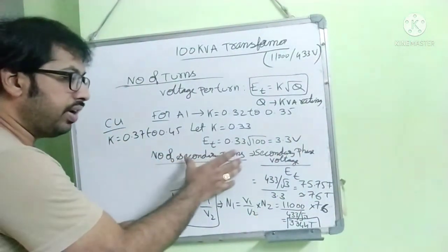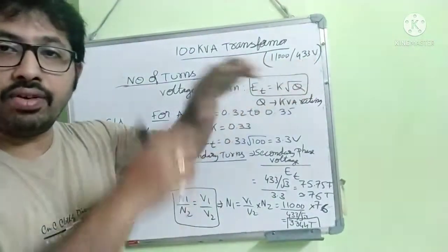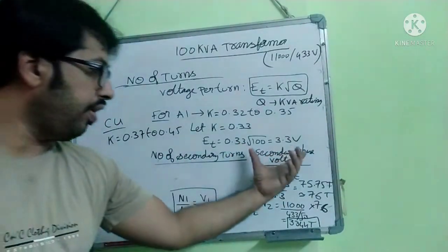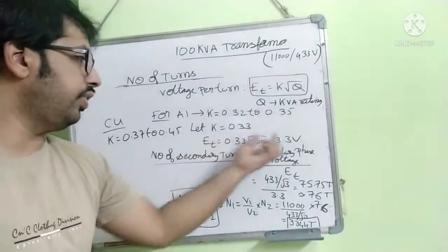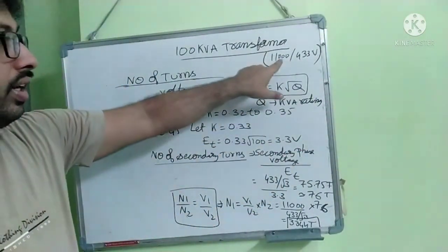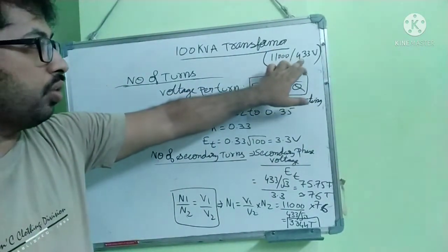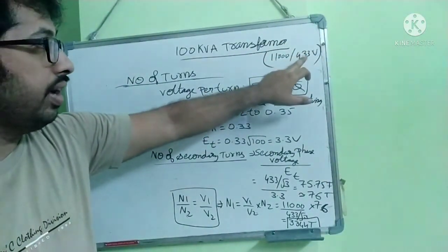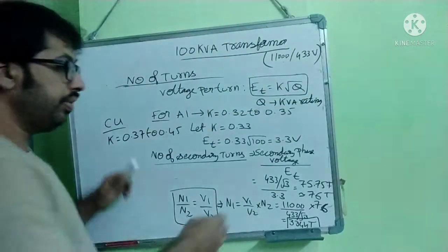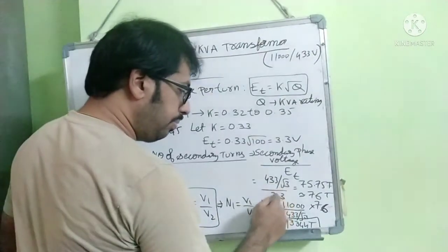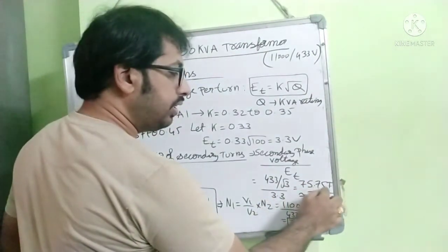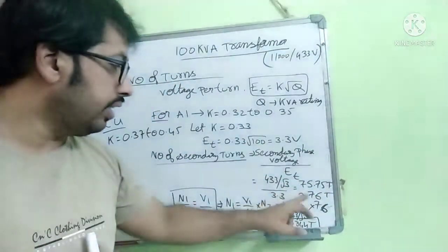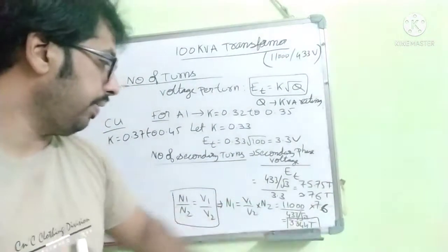Now we will find the number of secondary turns. Secondary turns means LV winding. Secondary turns is secondary phase voltage by the voltage per turn which we got. This is actually delta star. So how to calculate the phase voltage? 433 by root 3, that is the phase voltage. The one which is given is the line voltage. So secondary voltage 433 by root 3 by EMF per turn is 3.3. We got 75.75 turns, which we take approximately 76 turns. So LV winding has 76 turns.